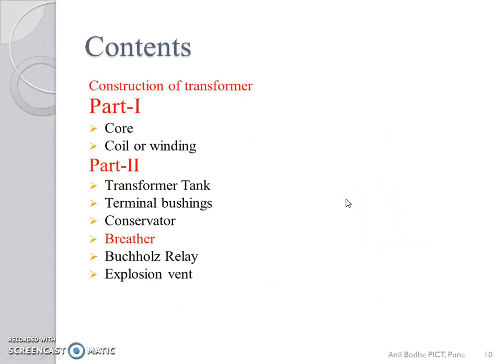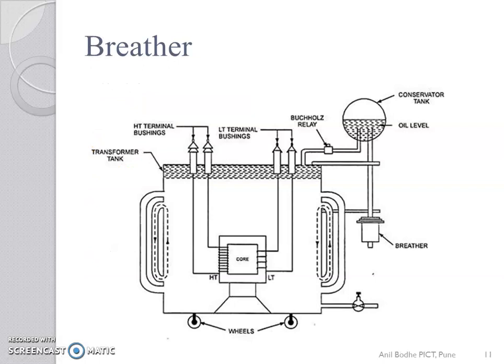Now, breather. The breathing process of the transformer takes place through the apparatus known as breather. It contains a drying agent such as calcium chloride or silica gel which extracts the moisture from the air. The breather also cleans the air by removing the dust particles present in it. Thus, only dry and clean air is allowed to come in contact with the oil in the transformer.